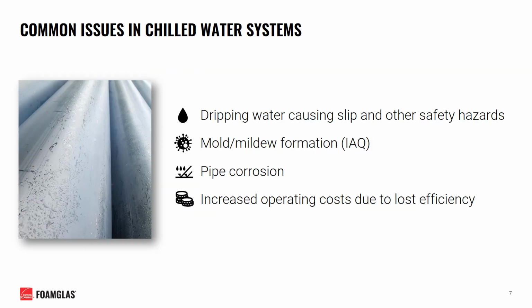Here we can see some of the most common examples of those issues typically found on failed chilled water insulation systems. They include dripping water causing slip and other safety hazards, the formation of mold and mildew, obviously a problem for indoor air quality, the corrosion of the metal pipe or other nearby equipment, as well as increased operating costs due to the loss of insulation efficiency.